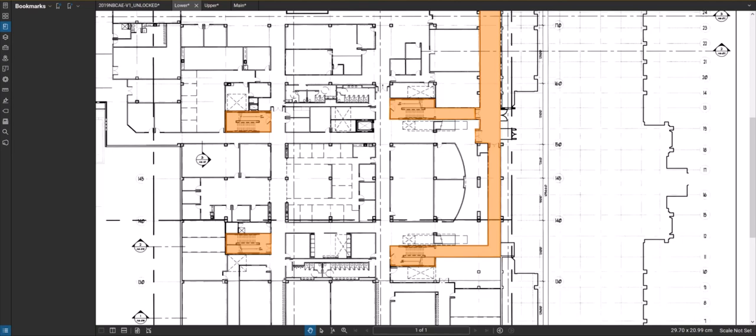Just going back to the plan here, this is where the pictures were taken. One was standing right there, looking down that corridor and seeing that stair where you're going underneath the landing. And the second picture was looking down here. So if you go back to that picture, you'll see the double doors there in the background. And if they didn't clean them out, get rid of the storage out of there, what would I do? The next step would be I would phone the fire marshal or building inspector, someone like that, to get a direction formally sent to them saying you can't store stuff in there.